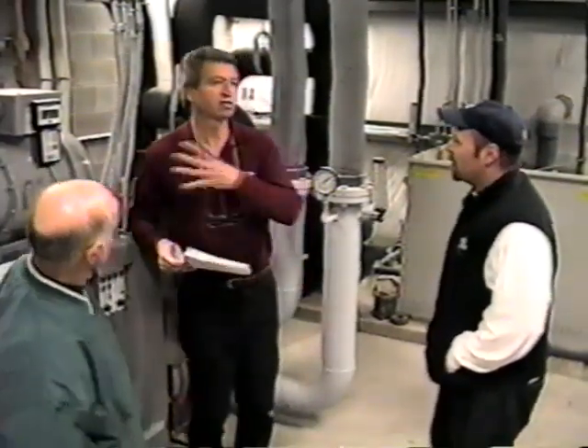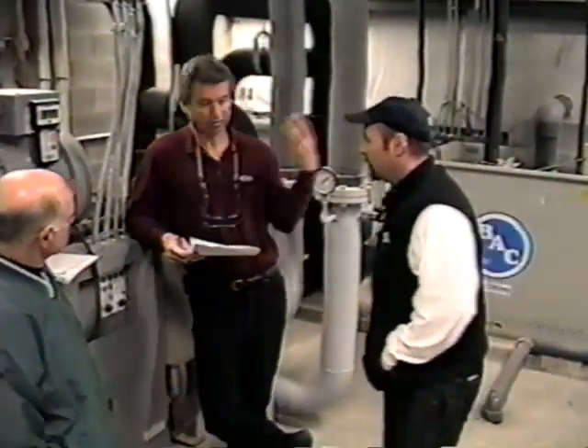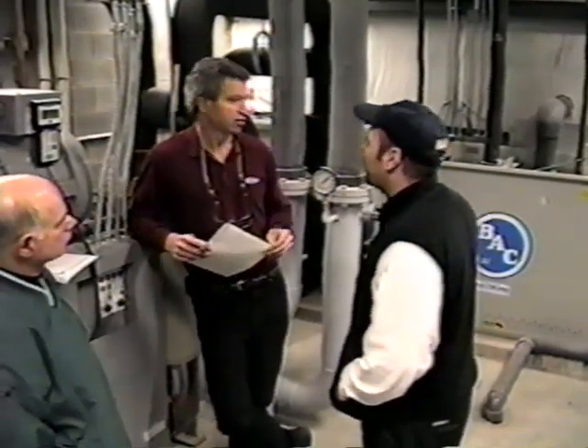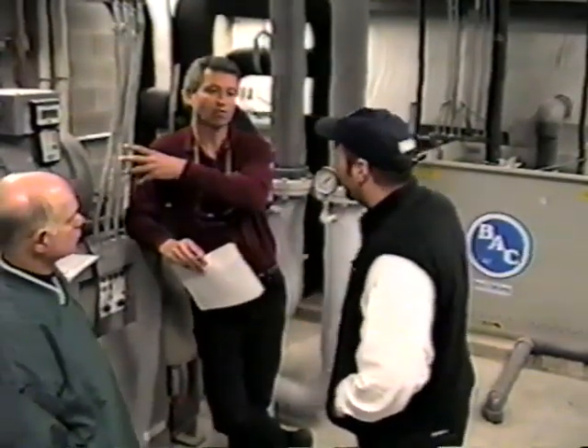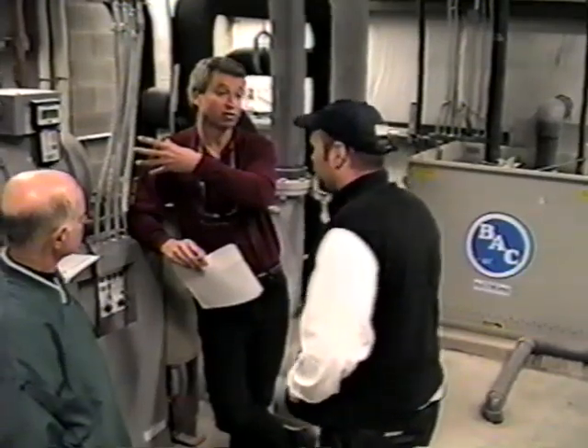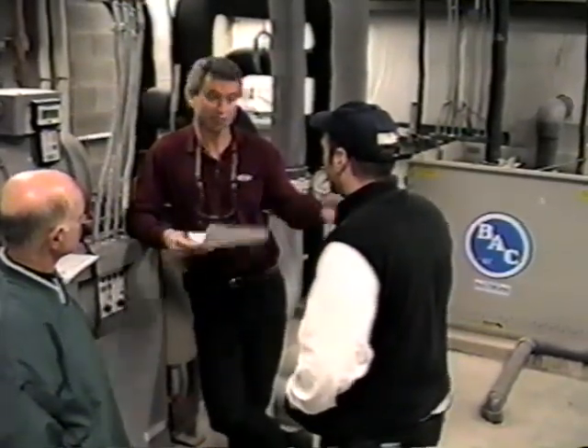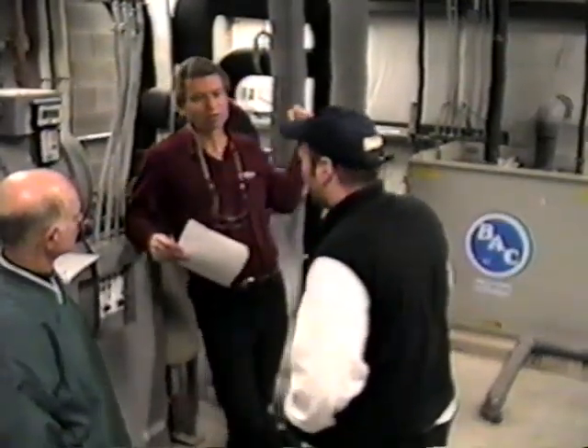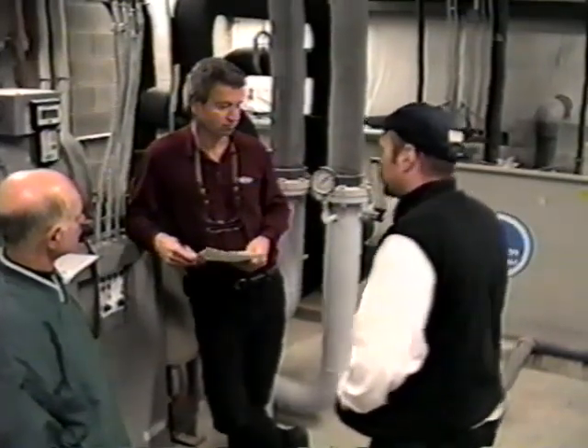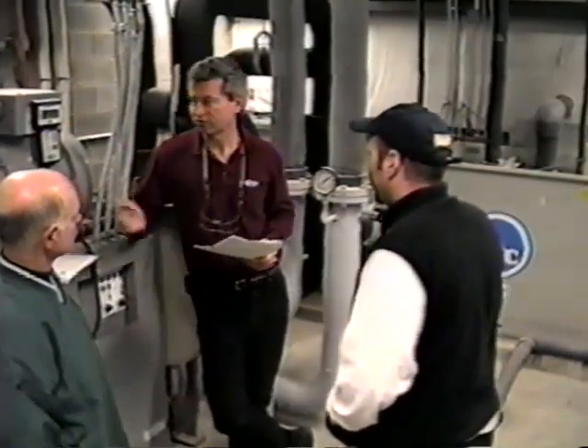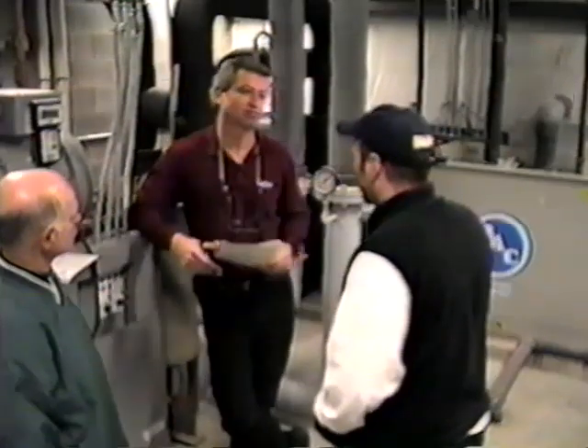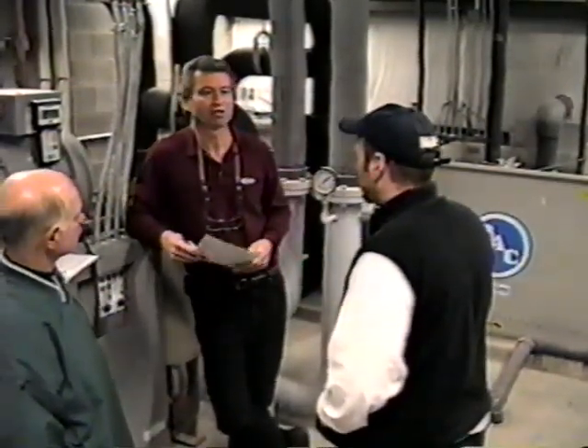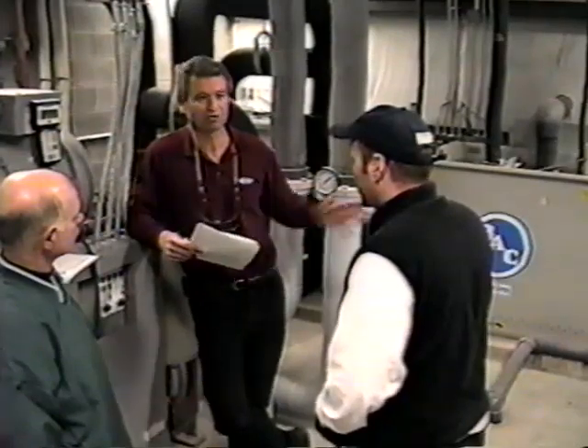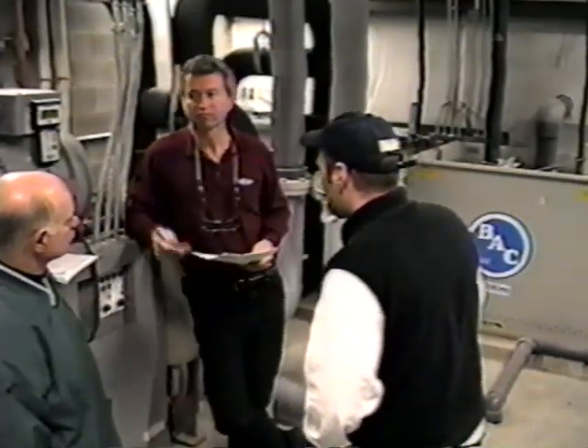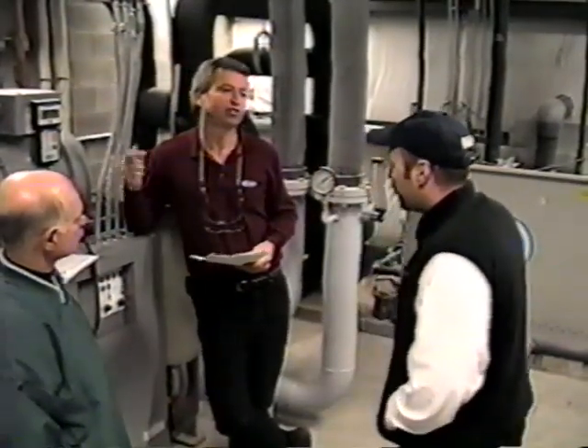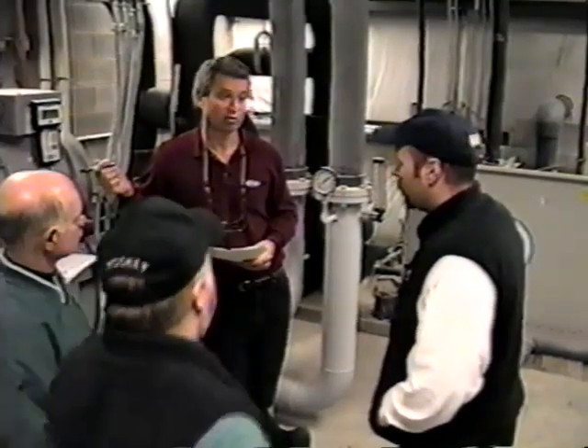So, I mean, this is kind of independent from that whole system. You're going to see an alarm, high discharge pressure. From that, obviously, you're going to think about what would cause that. Will you be able to manually do anything from the machine to start and stop, like your main panel there? No, because it's not really an electromechanical type of system control. But at least you know what it went off on as far as discharge pressure.